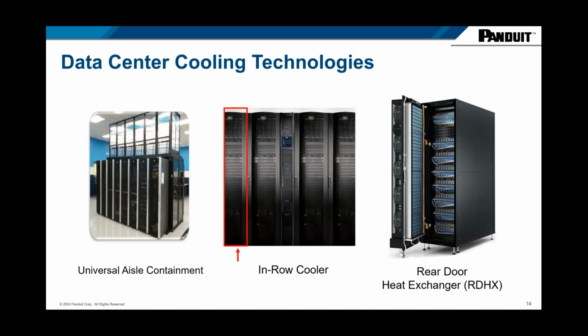Visually, for those not familiar - universal aisle containment is a complementary system to help with air-cooled systems like you see in the middle with in-row coolers. On the right is the rear door heat exchanger - like a big refrigerator door that bolts on the back of the cabinet, with cooling elements inside to help transfer heat out. It's a closed contained system but there's air in there, and you can assist with liquid or air. Basically it attaches to the back of the server cabinet and helps dissipate heat as you go forward.